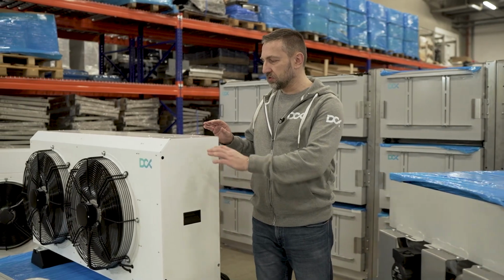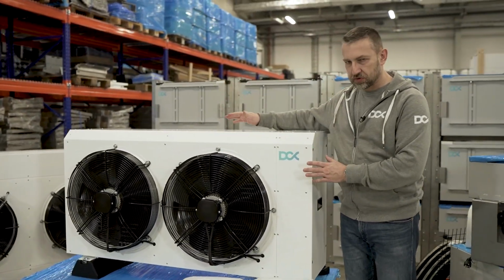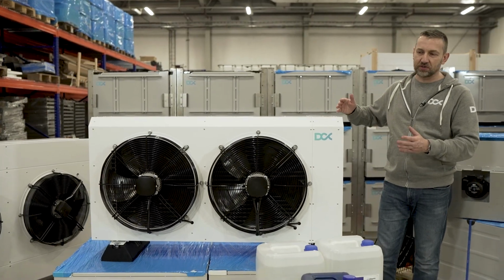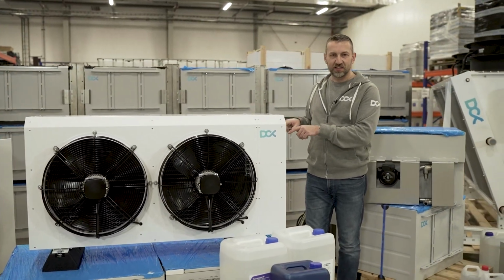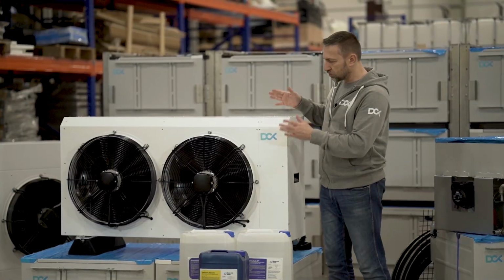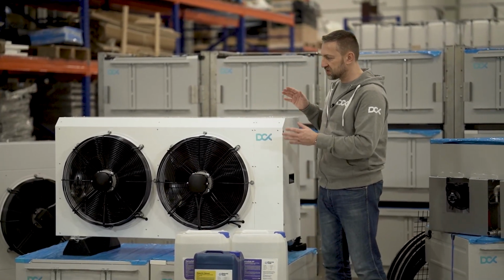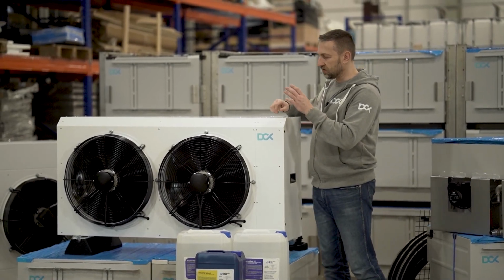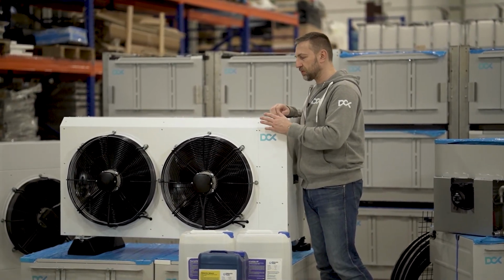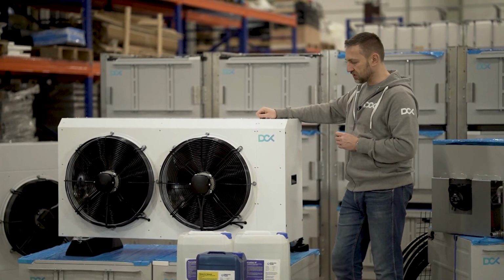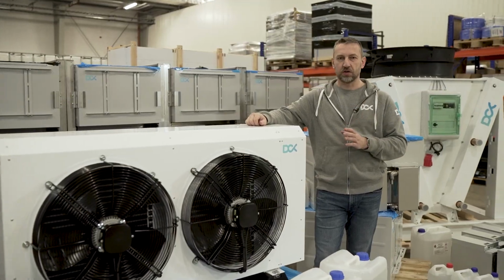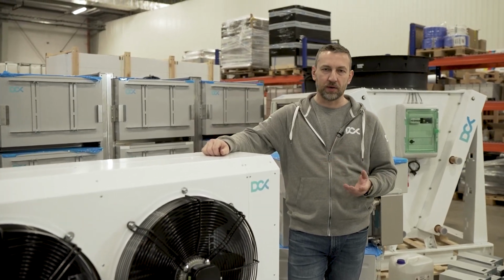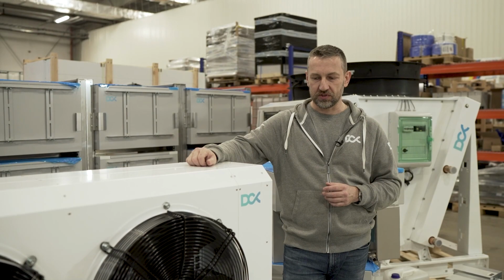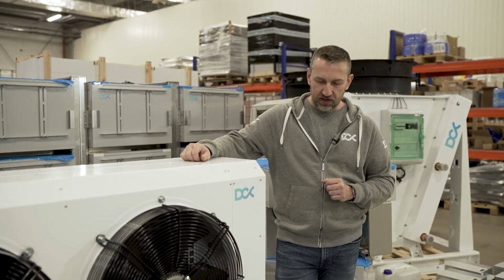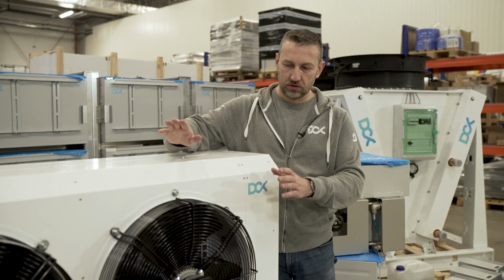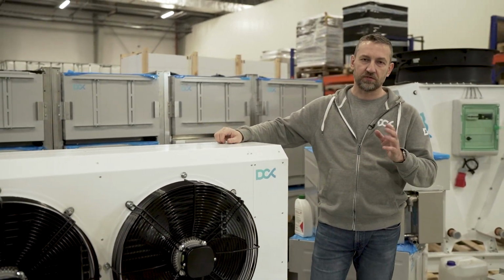The other unit which we have is the ICP40, a dry cooler integrated with the pumping system, which is hidden inside that pump compartment. We are using two 500 millimeter fans. These are 50-60 hertz fans, which take 320 to 340 watts, depending on the fan model, because we are using different vendors, relying mostly on the most recognized Ziehl-Abegg or EBM, the two best brands we can get in terms of fans for dry coolers. And the system has dual fans, so they take approximately 700-750 watts.